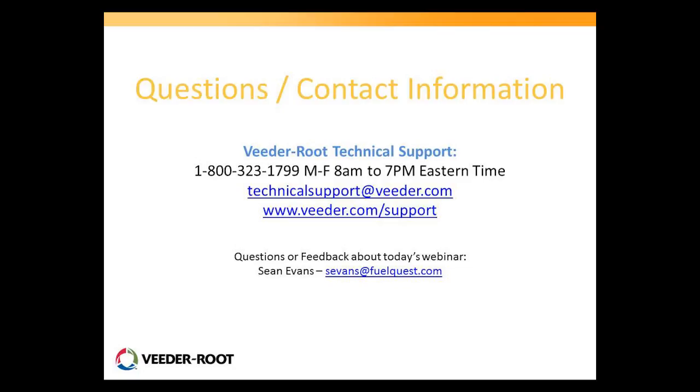Okay, great. Thanks, Lee. One other question here. Is there an advantage of an annual tightness test versus performing a monthly method for compliance? Sure. Okay, so if you were monitoring electronic lines on a monthly basis, we call that risk management. And the reason we call that is that the system's going to try to run a 0.2 gallon per hour test as often as possible when it sees the opportunity. If you have a leak of 0.2 gallons per hour under your dispenser, for instance, at a union or at a meter, you're going to be able to detect that. The system doesn't shut down because you can program it not to shut that down. It tells you you've got a problem. You go investigate and you find the leak and you repair it.